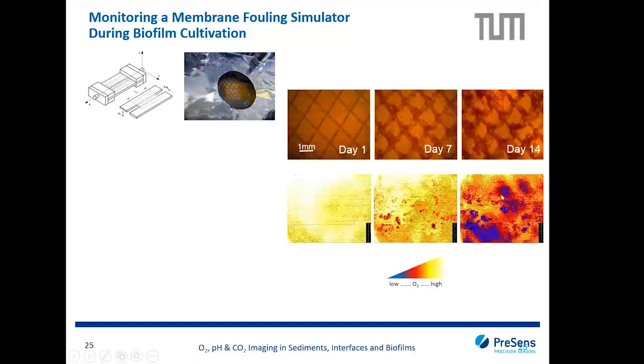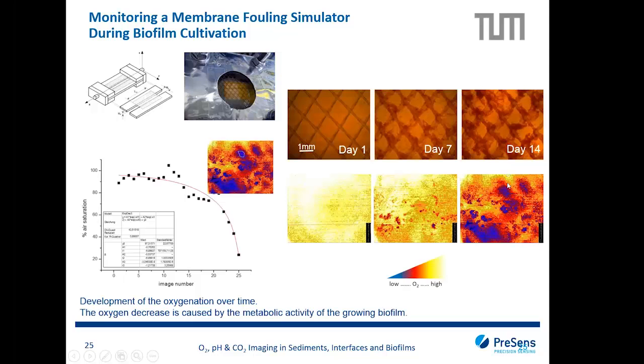And what you can also see here, if you compare the raw sensor response with the oxygenation image, is that even if there are large volumes of biofilm, that doesn't necessarily mean a huge oxygenation drop. So the biofilm can have big volumes, but the respiration rate can be different. So with oxygen imaging, you can define the respiration rate. And you can do that, for example, by choosing an arbitrary ROI at a specific position and getting the oxygenation drop profile.